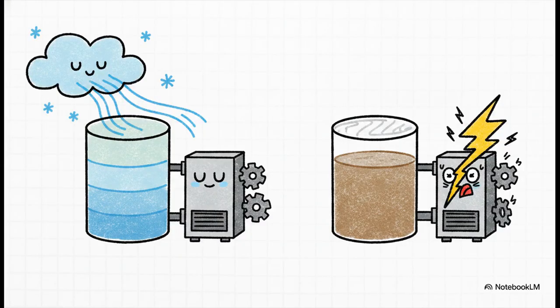And the efficiency gains don't stop at physical space. Keeping that hot return water completely separated at the top of the tank also makes mechanical chillers run far more efficiently. It's a concept based on optimizing the temperature difference, the delta T. Plus, modern data centers use economizers to capture eco-friendly free cooling from cold winter air outside. Stratification perfectly stores this low-grade cold water. If the tank destratifies, the stored water temperature rises above that free cooling threshold, forcing the facility to turn its energy-hungry mechanical chillers back on prematurely, wasting massive amounts of electricity.